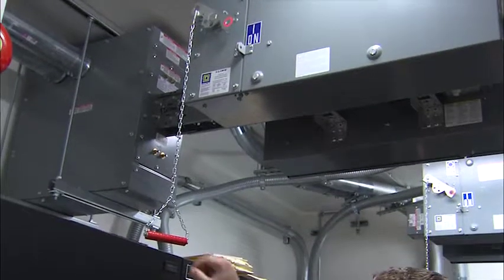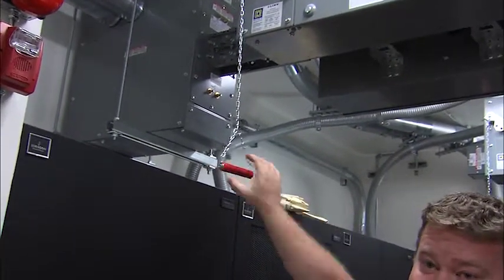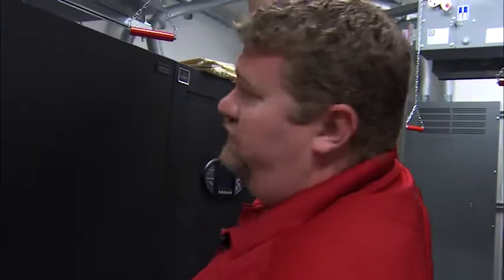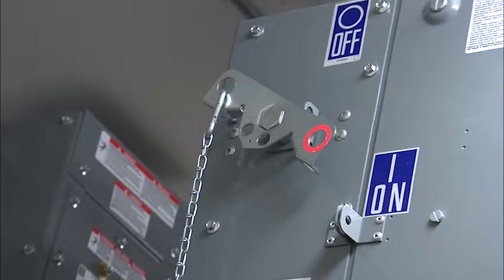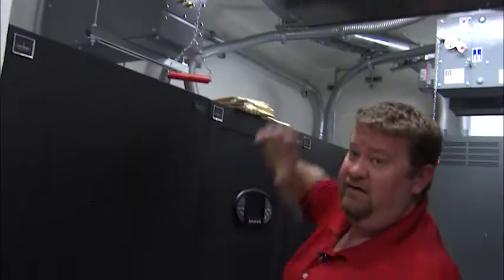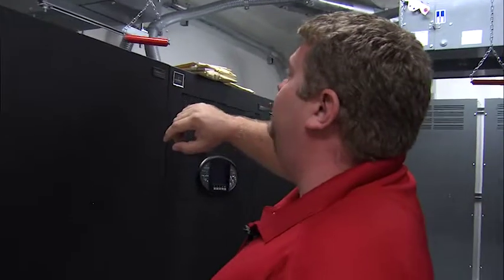Basically, once these are all put into bypass or EPO'd, you have no power path into these, because we don't want to synchronize the output of a UPS with the output of your utility, because one's clean and one's not. By code, we've got to have chains. You've got to hang on these to pull this breaker, just so you understand. Not literally hang, but you can't bump into it and trip it. Each one of these is a shunt trip plug breaker within this can, and this is just 400 amp bus, large cable. As you can see how large the pipes are.